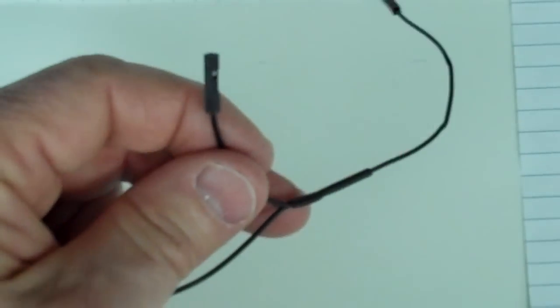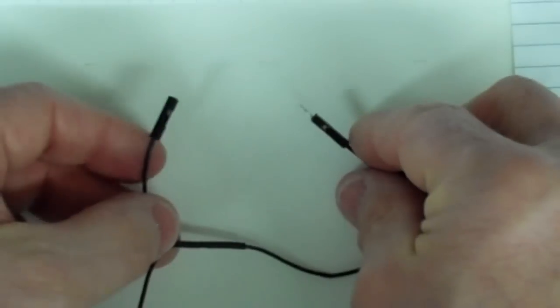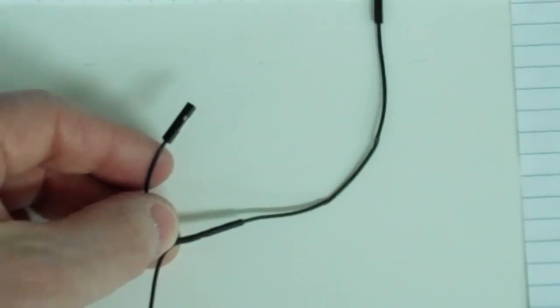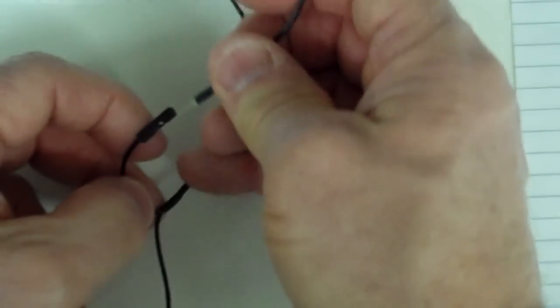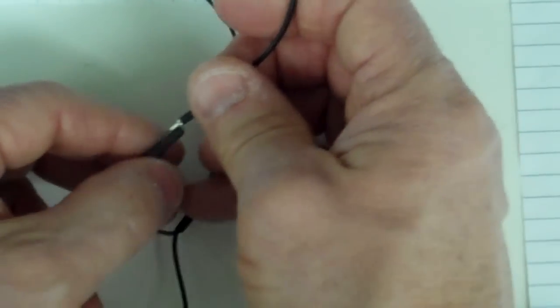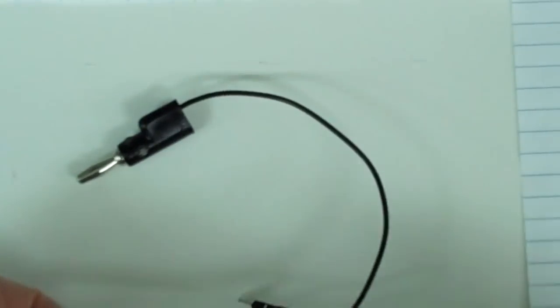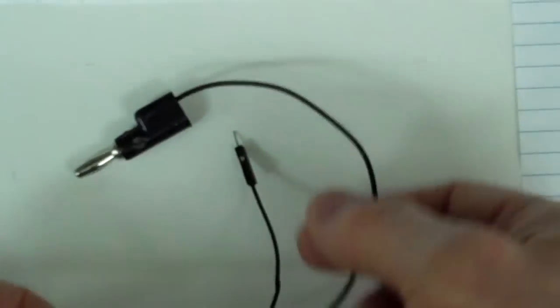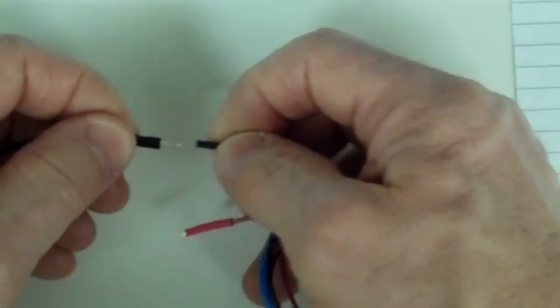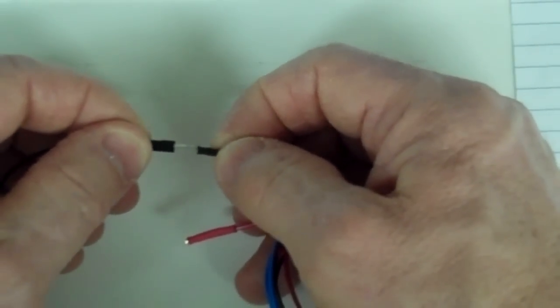Then, since the sensor requires a ground, and the meter that we monitor the sensor with also requires a ground, we'll connect the banana-ended wire to one of the Y junctions, so you can see that here. This will be the ground that goes to the voltage supply. And then the other end of the Y, the male part, would connect to the female of the sensor.